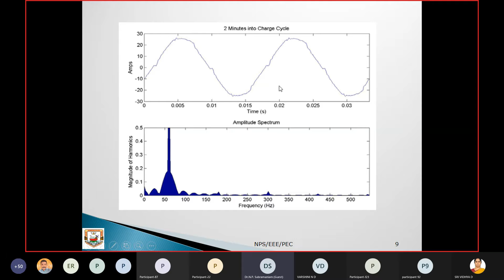If you go to 134 minutes, that is more than 2 hours, we can see due to harmonics accumulating, the waveform's nature becomes totally abnormal compared to the sinusoidal waveform or the previous waveforms. That's why the THD compared to the previous plot is much higher, and it will affect the system.